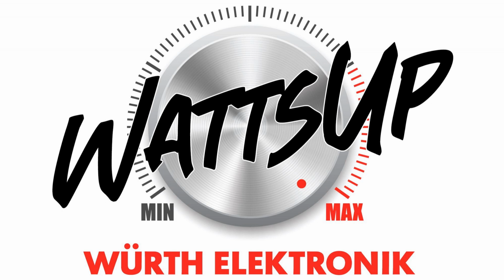and this could help a lot if you want to pass conducted emission. The thing is, when you use that kind of nice metal boxes with excellent filtering, you have to take care that they act on both noises. They act against common mode noise, which means on both phase and neutral comes absolutely the same noise. What is acting in this case is the common mode inductance, like the name says, common mode choke, and you have these two Y caps.